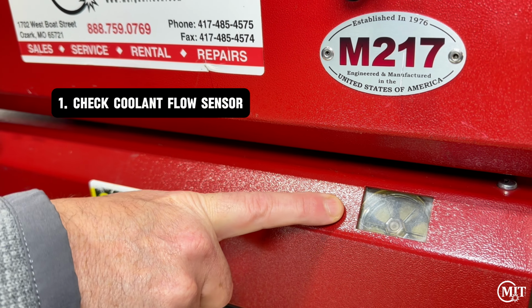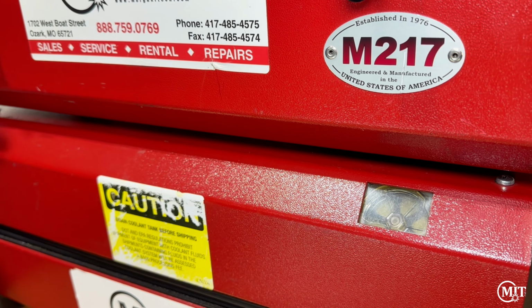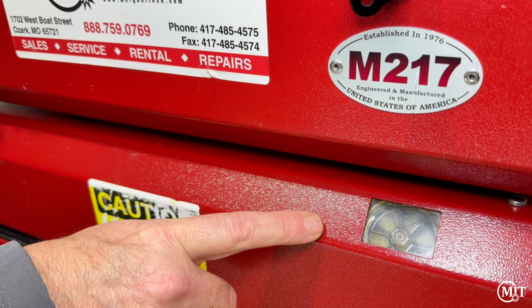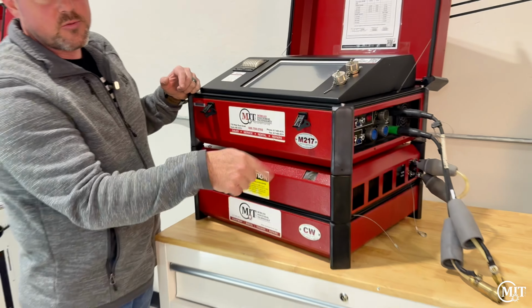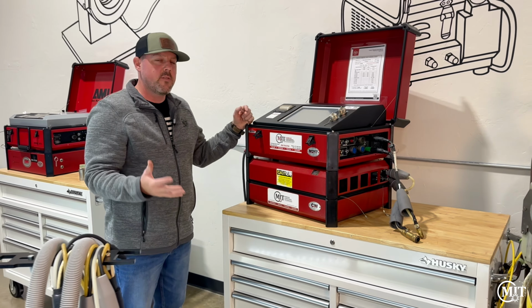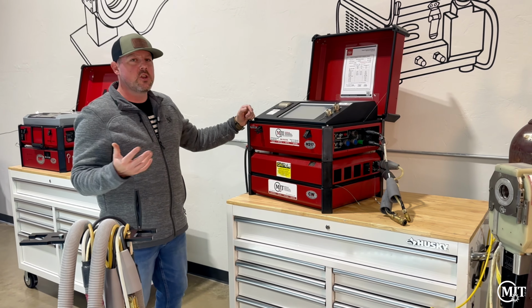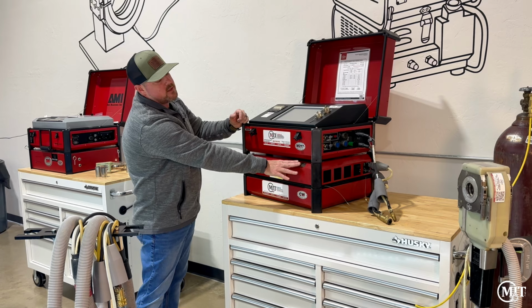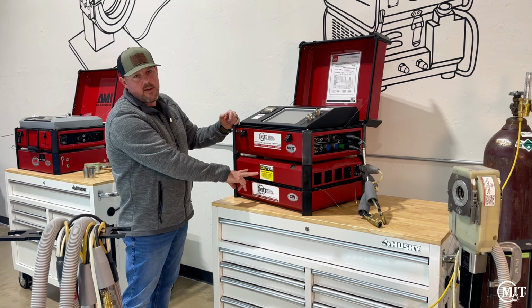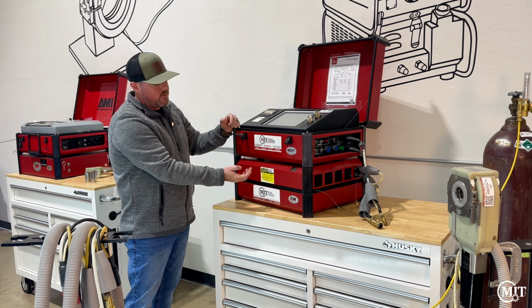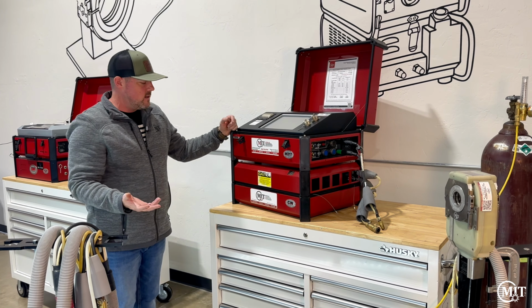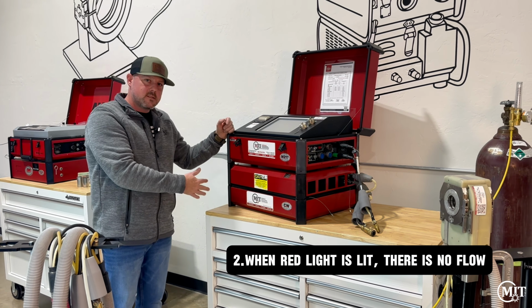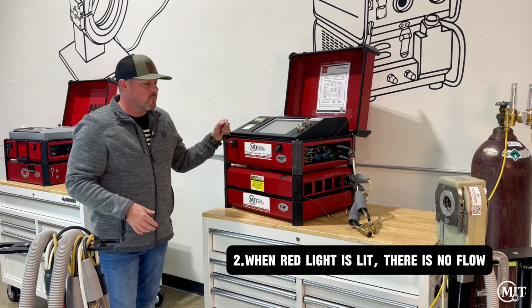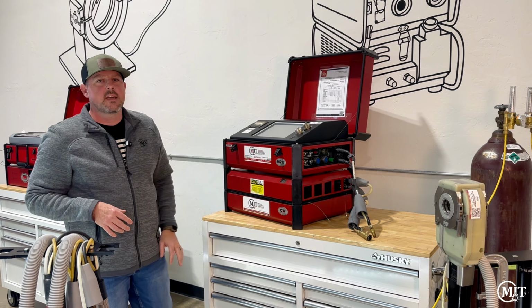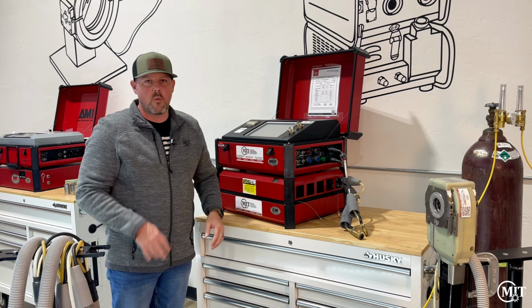That coolant flow sensor has 5 different little fans inside. When you have coolant flow, that is rotating. When you don't have coolant flow, it's not rotating. Some of the newer coolers, instead of having the window, have a red and green light. If the green light's lit, you have flow. If the red light's lit, you have no flow. It's basically the same thing inside, just not a visual window.